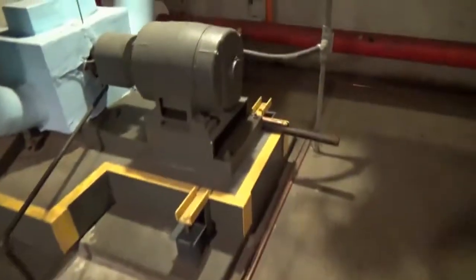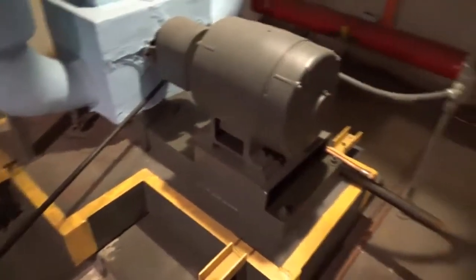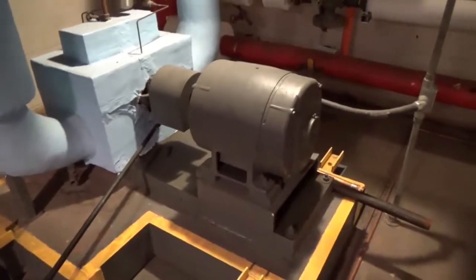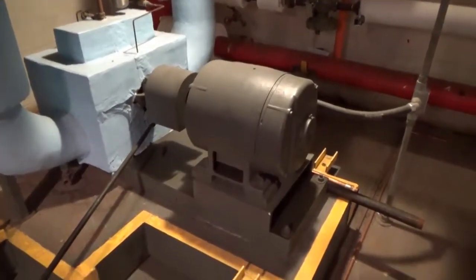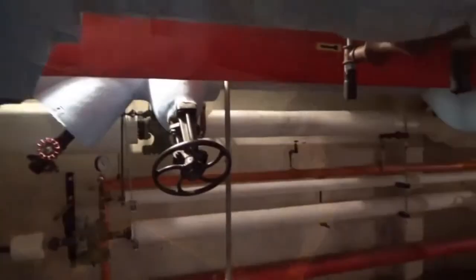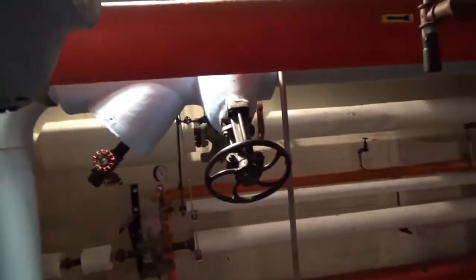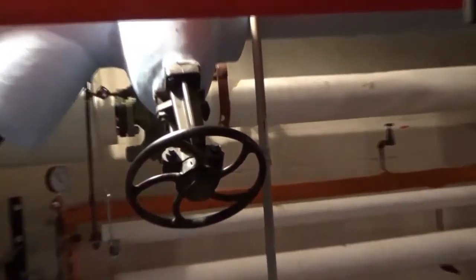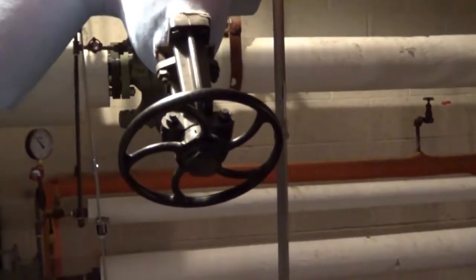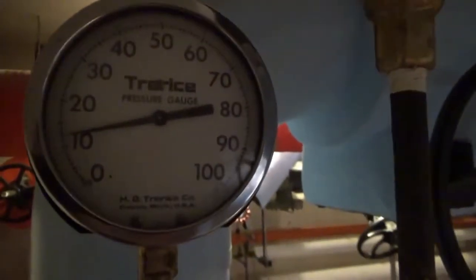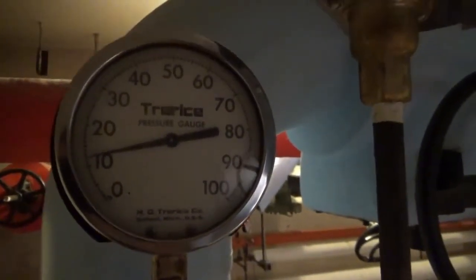We have another pump that's identical, and it's a chilled water pump, but again, to my understanding, this pump very seldom gets run, and this valve stays closed, and very seldom do we have to open that unless we would ever have to run that chilled water pump. We have enough pressure coming up into the building that we don't need the pump. As you can see, we're running at 11 to 12 pounds psi, and the pump's not even on.